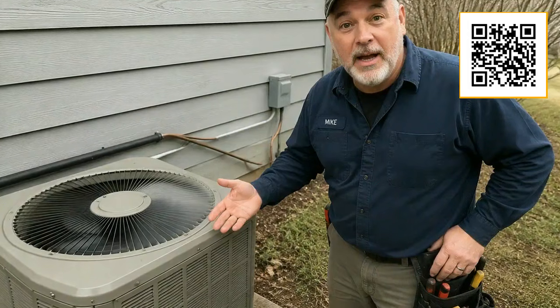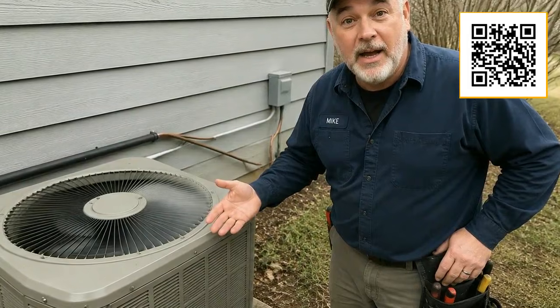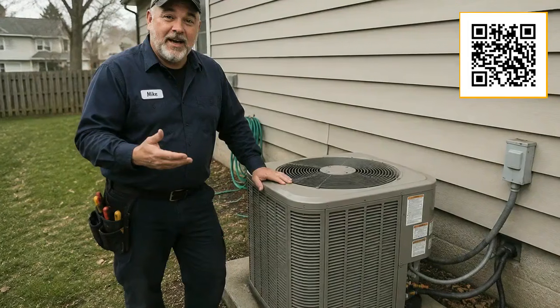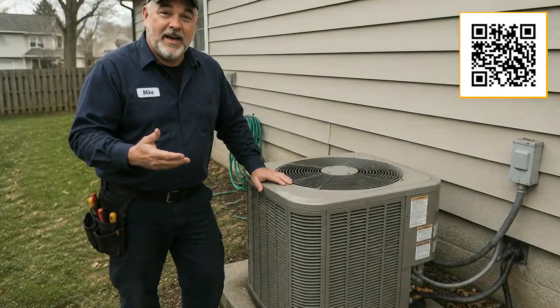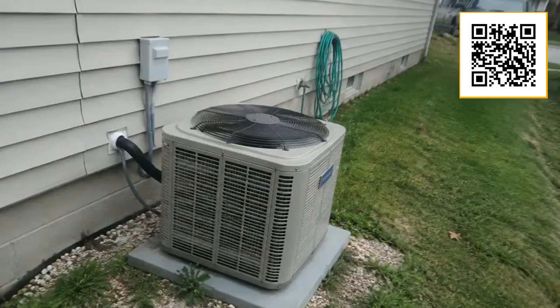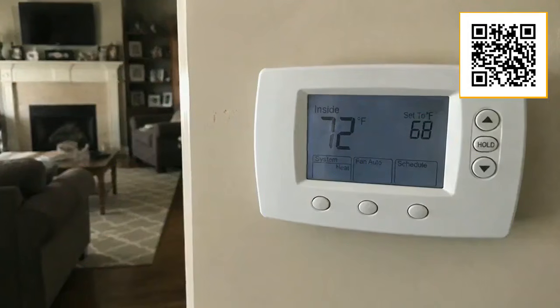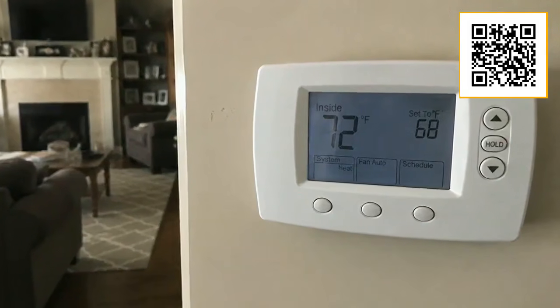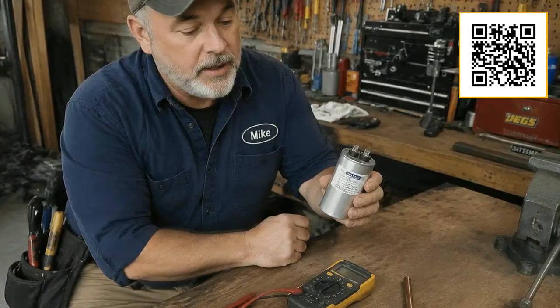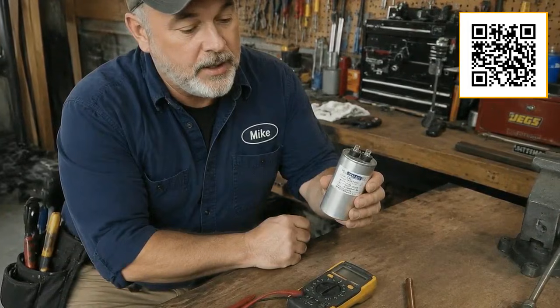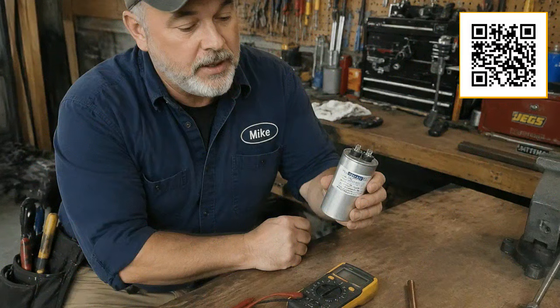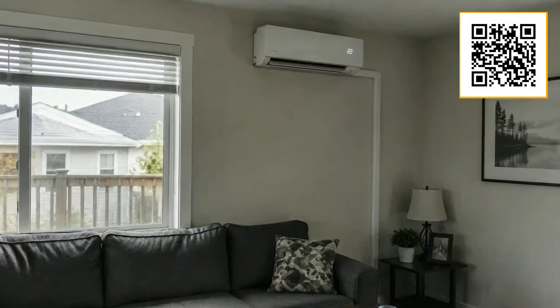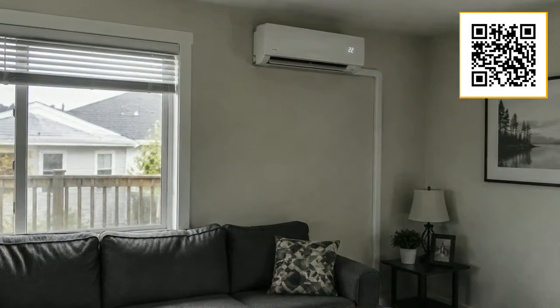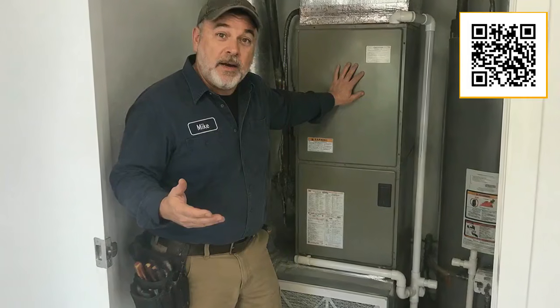Number 3 is single-stage units running in climates they were not designed for. A single-stage air conditioner is either all the way on or all the way off. There is no middle setting. In a mild climate with moderate summers, that works fine. But in a hot, humid climate where the system needs to run for long stretches just to keep up, that constant full-blast operation creates wear that adds up over time. I have seen single-stage units in southern climates fail noticeably faster than their two-stage or variable-speed counterparts doing the same job. The variable-speed units run at lower capacity for most of the day and only ramp up when they need to. That is easier on every component.